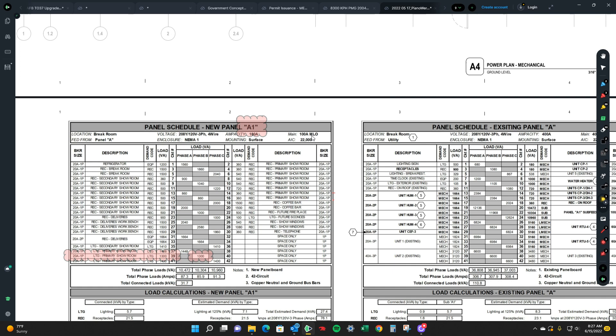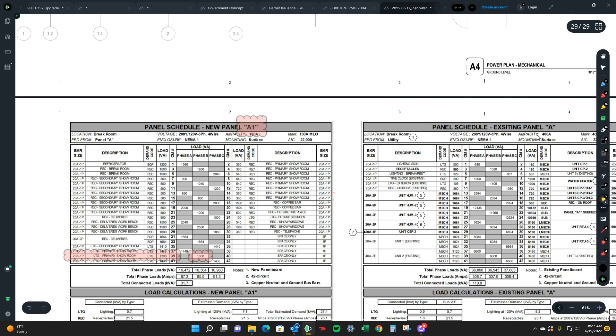So that typically means that there is a breaker nearby that's within sight. It's located in the break room. It's fed from panel A, which would be this guy. And then it's 208, three phase. So it's three phase, 120, 208, four wire, which means it has a neutral, which obviously it should.